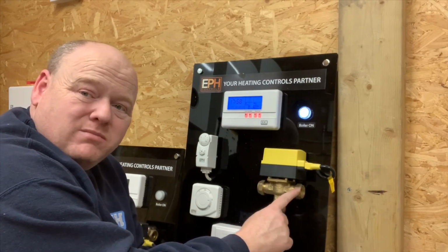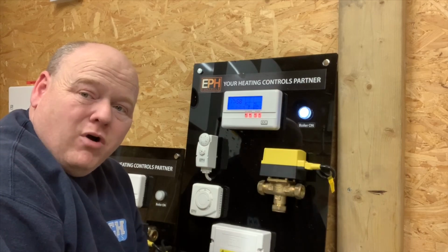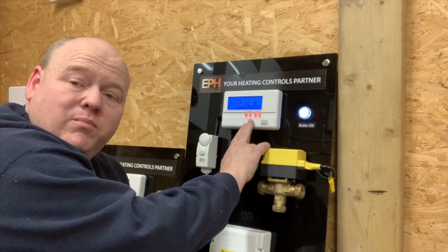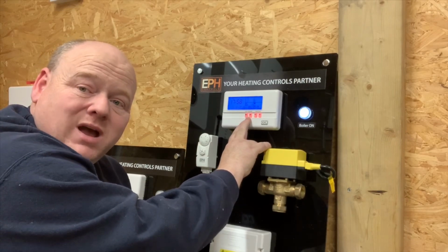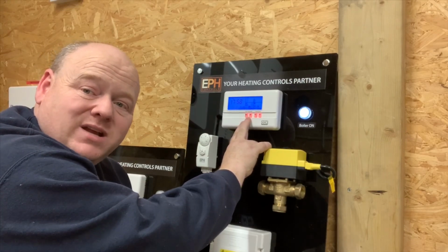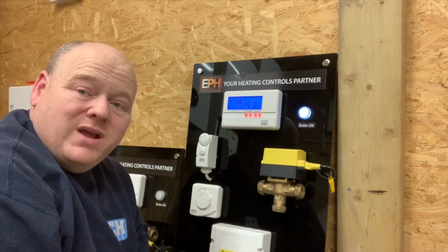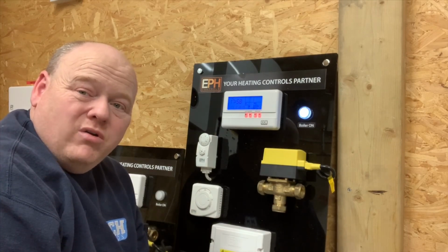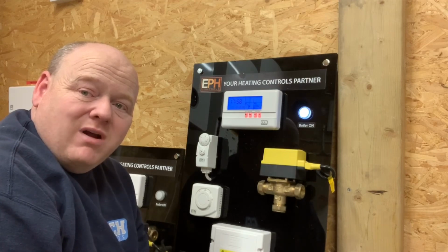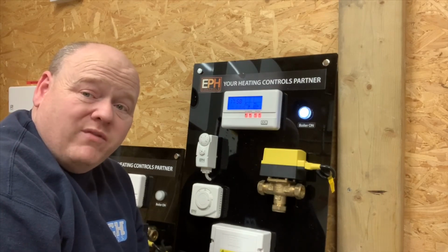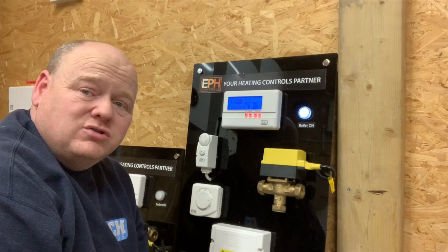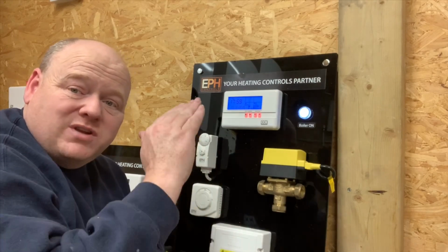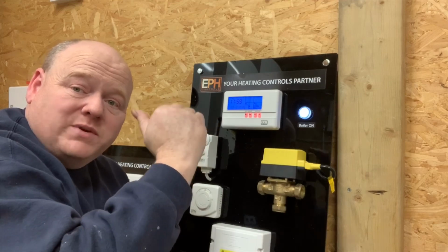So if you've got a system that's struggling a little bit, or in the morning it takes a long time to warm up, then it may be that if you put your hot water timer at a different setting to the heating, when you put your heating on, it would get warm quicker. So what I would normally advise customers is to rather have the hot water on 24/7, so never turn it off. It doesn't mean that it's on all the time. It just means that if it drops the temperature a little bit, it'll just top itself up.